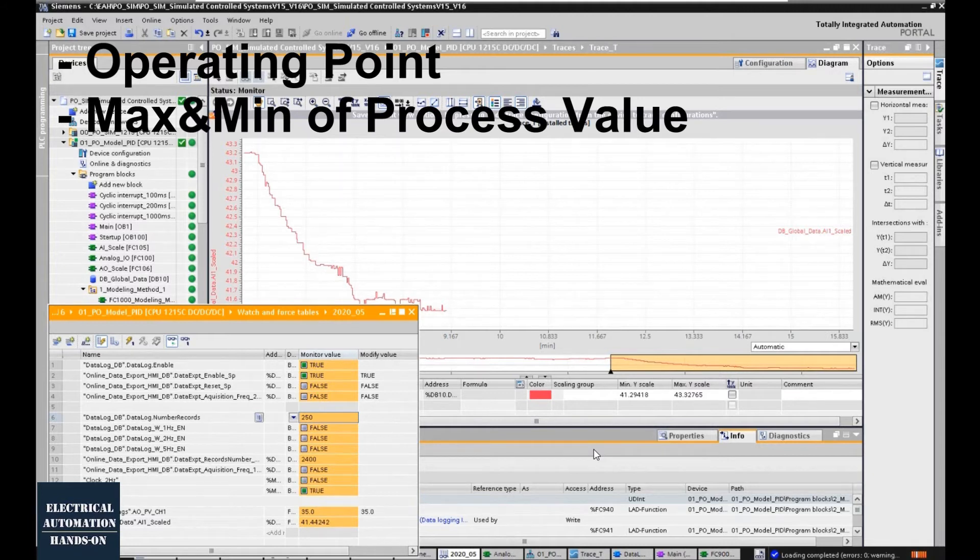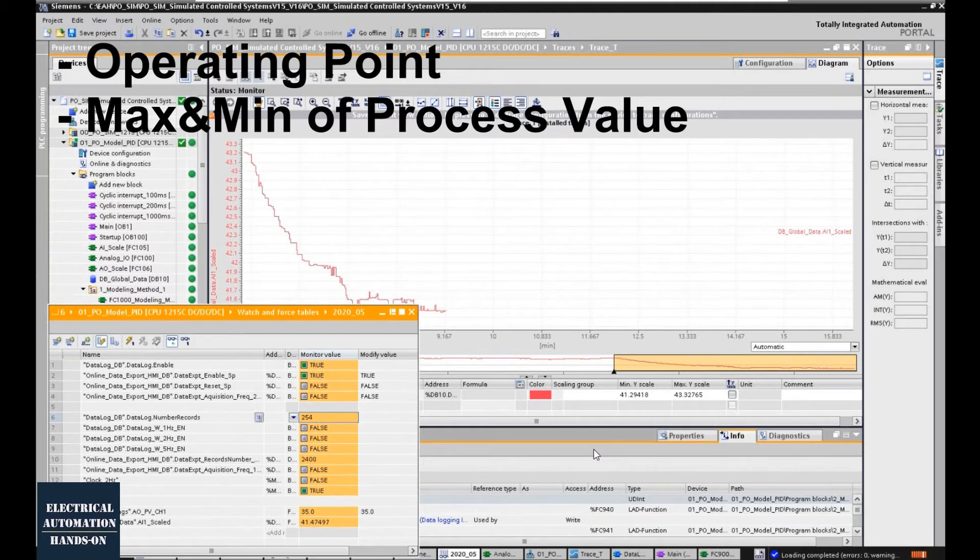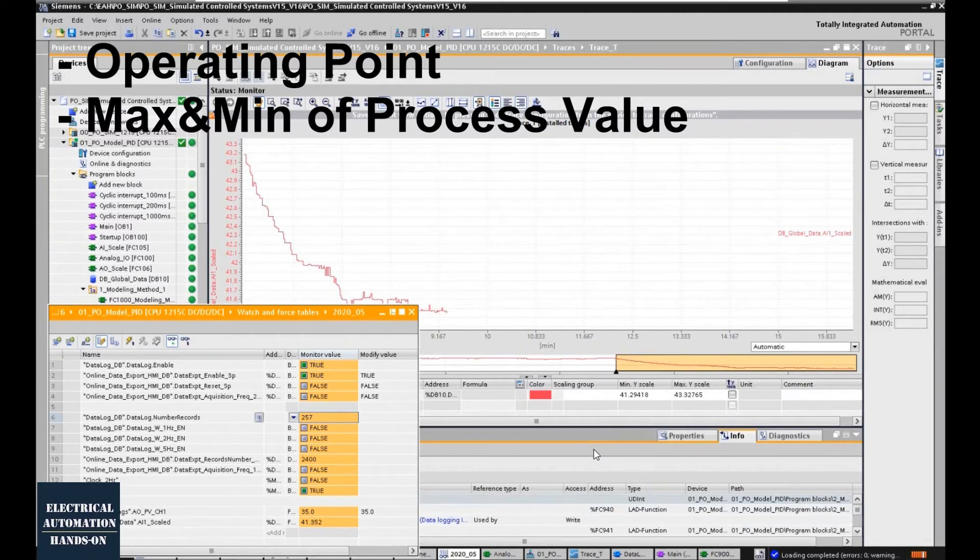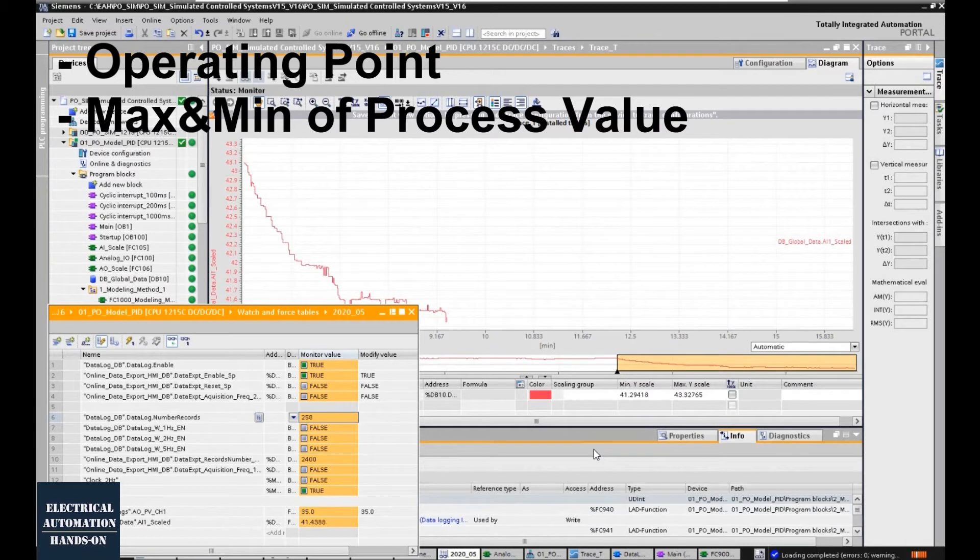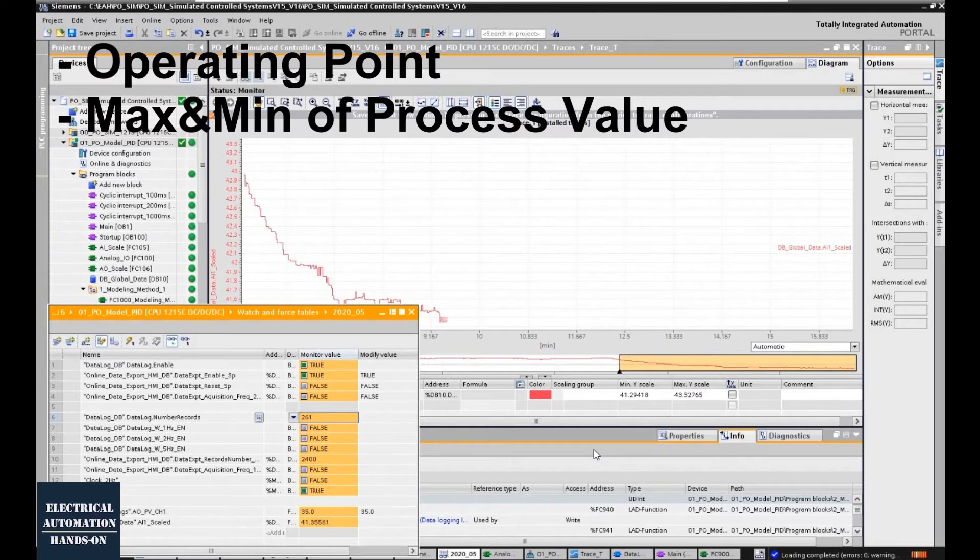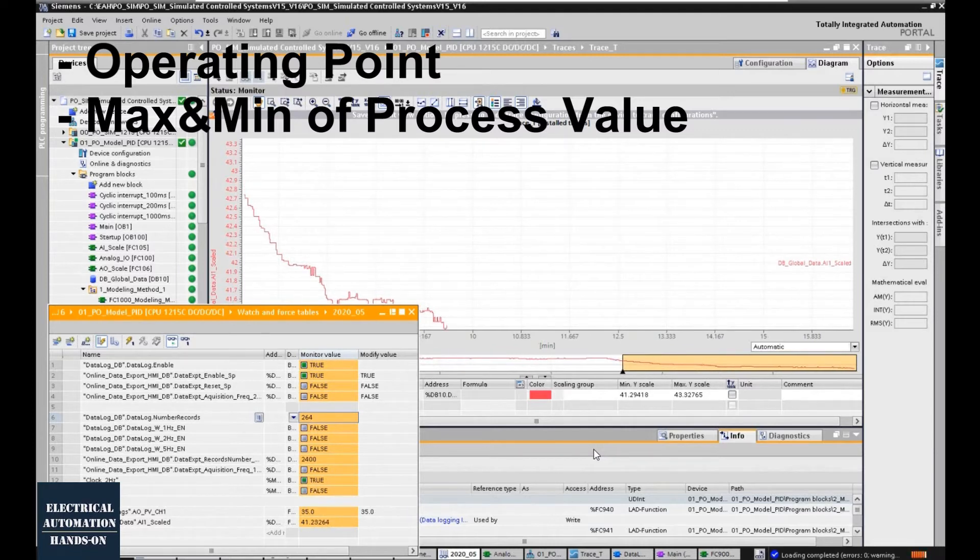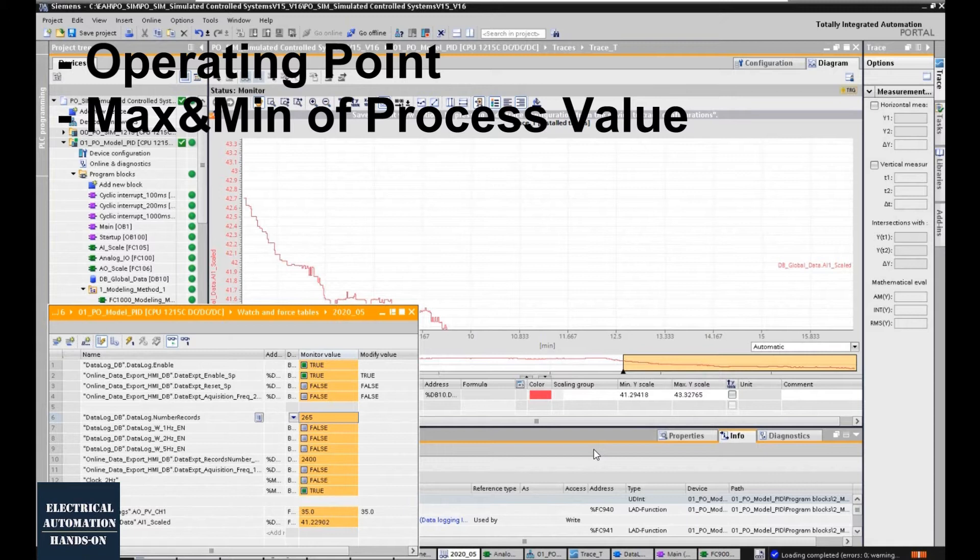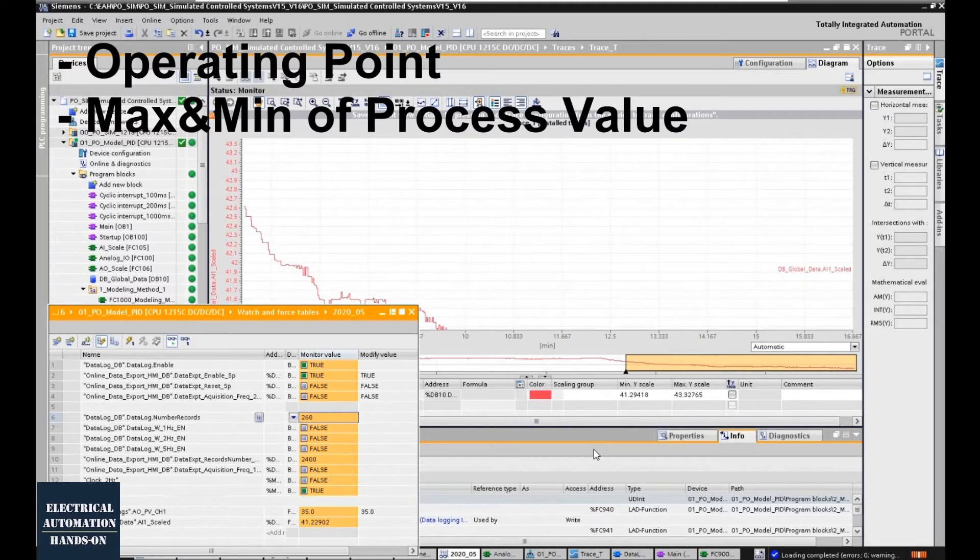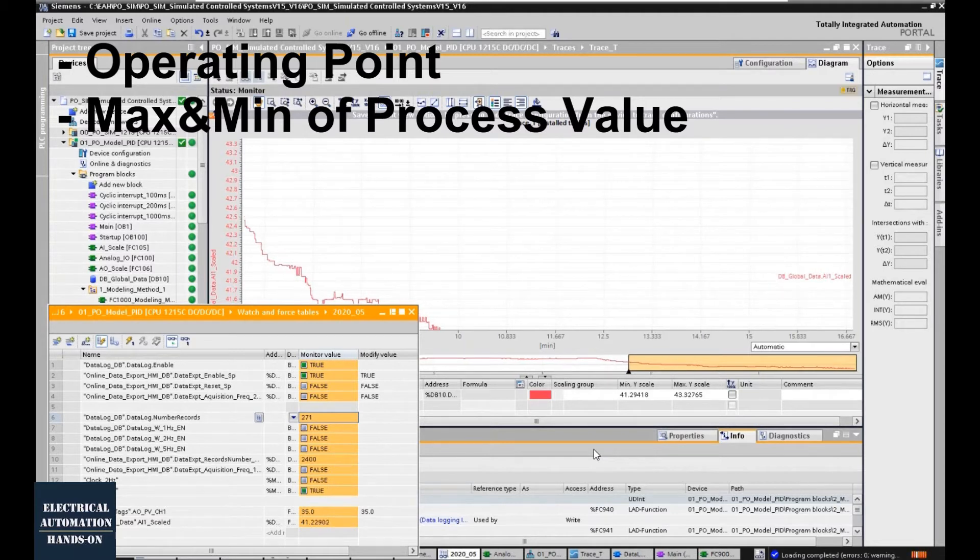And the second item is the maximum or minimum of this process value of your system. Especially when your actuator opens to 100 or closes to 0, what the maximum or minimum value your process could be. Because sometimes, even if your actuator already opened 100%, your process value still cannot reach that set point. Take a heater system as an example. Maybe you already regulate 100% on your heater energy, but the temperature still cannot reach that setting point or the target temperature. That means maybe the design has something wrong. It's not only the control issues.